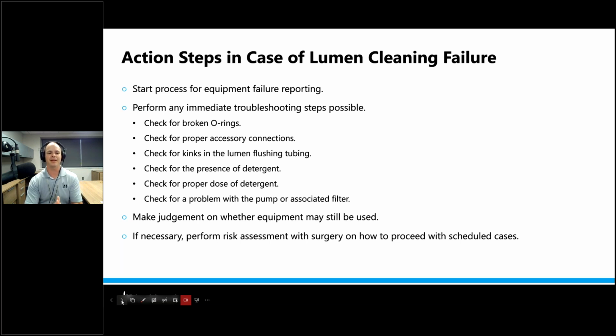But perform any immediate troubleshooting steps as possible. Check for broken O-rings, check for proper accessory connections, check for kinks in the tubing, right? Check for the presence of detergent. Check for the proper dose of detergent if it's possible, right? Check for a problem with the pump or the filter that's associated with it, all right? Sometimes those pump filters that I showed you get so gunked up, and over time they're still trying to use it, that the actual pump goes bad and there's no pressure showing on the pump gauge. So there have been times where both the filter and the pump had to be replaced. So if you have in your preventive maintenance plan to have somebody check that filter every so often, hopefully you can avoid a more costly pump exchange.